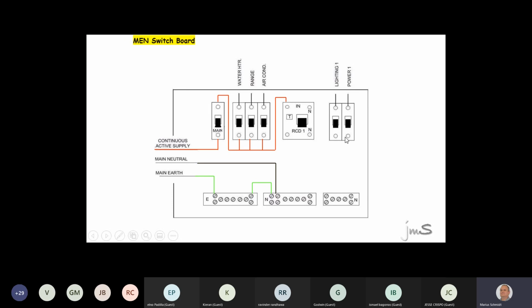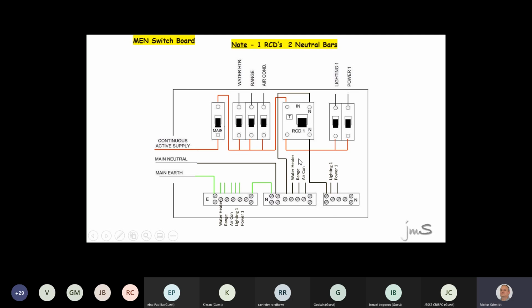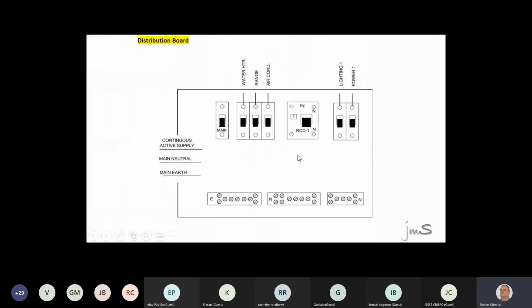And can you see that these 2 circuit breakers are fed from that RCD? Now guys, every RCD has got its own neutral bar. So this neutral feeds that one, and this neutral feeds that one. So we call this the protected RCD neutral. So this neutral bar is for those 2 breakers. You guys happy with that? Correct, and I'll show that very shortly as well. So guys, to carry on, you all agree, 1 RCD, 2 neutral bars. Main neutral, RCD neutral. Happy? Right. Now, look at this one. This is a DB. Right, guys? Where is a DB fed from? MEN board. Did you hear that?